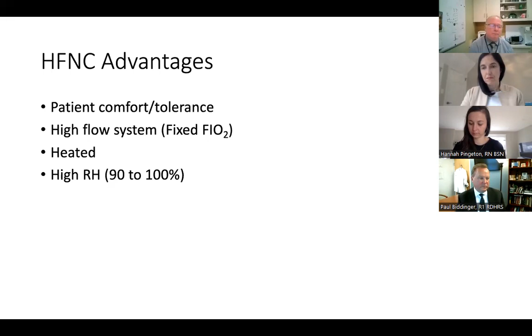The high flow effect that I mentioned is really twofold. We believe that there's a washout of a portion of the anatomic dead space which contains exhaled CO2. And on the next breath, that CO2 would normally be inhaled, which means it has to be eliminated through minute ventilation. So washing out a portion of that anatomic dead space can reduce the patient's work of breathing. It's also clear that they provide some level of CPAP, although we can't measure it. Studies have been done putting transducers in the larynx and looking at what the pressure changes are at different flow rates, and CPAP is definitely there, but it's not as much as one would think and is highly variable.